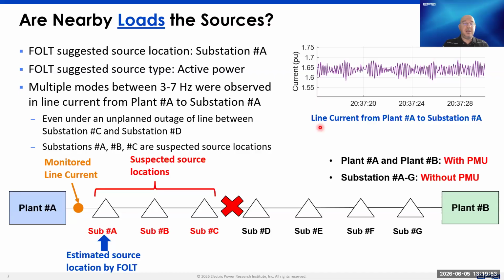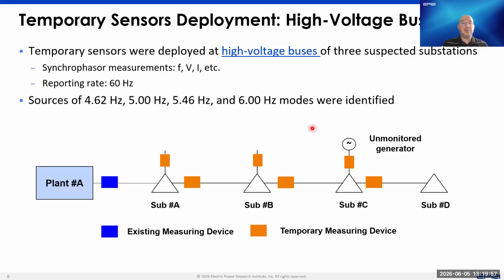Once we had that, the next step, in collaboration with Entergy, was that Entergy installed temporary sensors with PMU capability at the high voltage buses of those three substations. The orange boxes here are the additional temporary devices with PMU capability installed in those substations. They were installed within the substation to look into the feeders and the loads, and also on the line to monitor the current between substations. The data we could collect from these was frequency, voltage, and current at a 60 hertz reporting rate. This was very helpful.